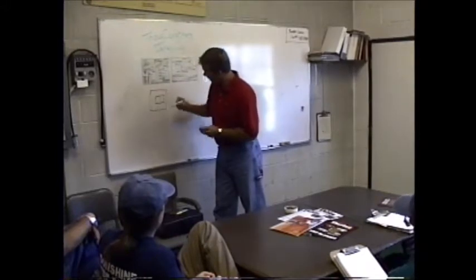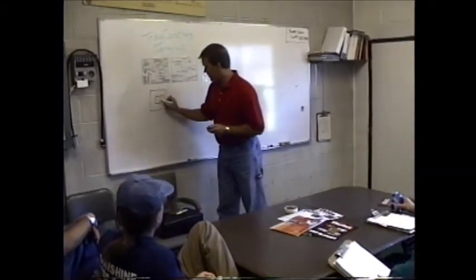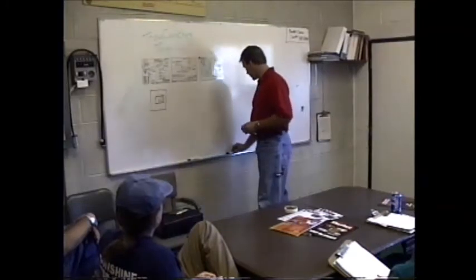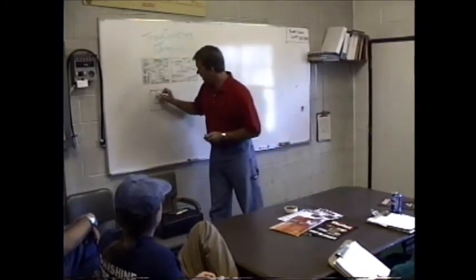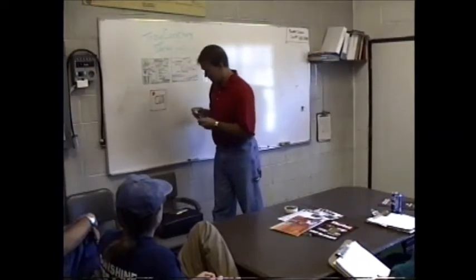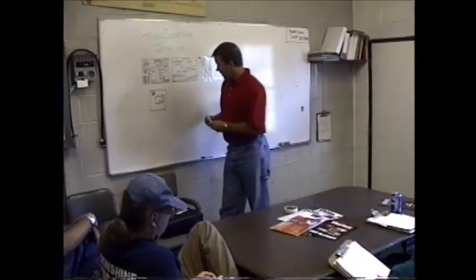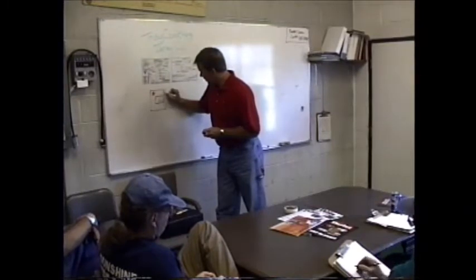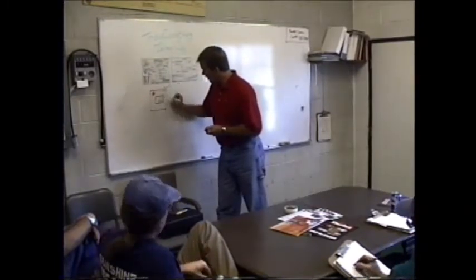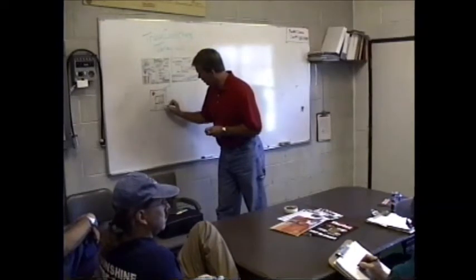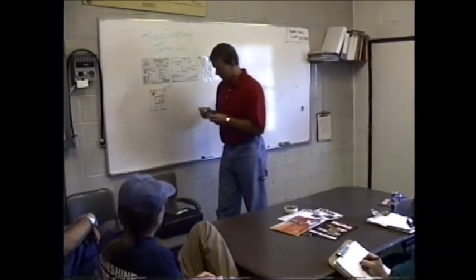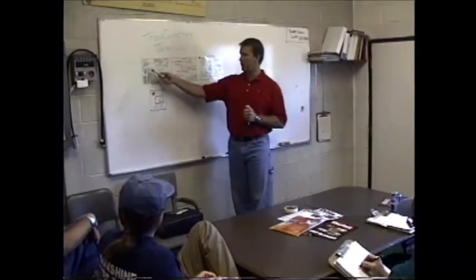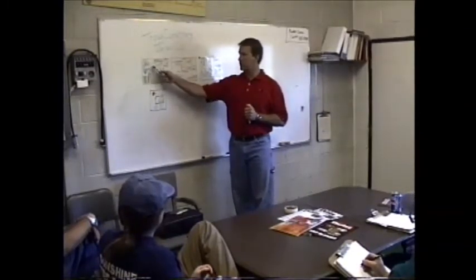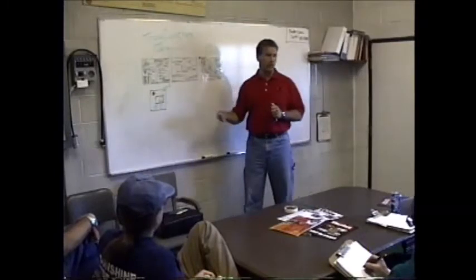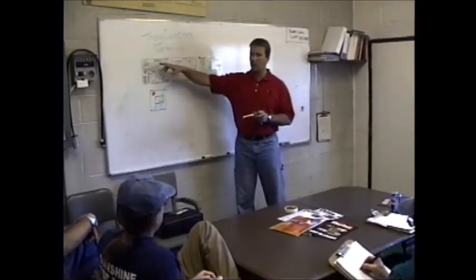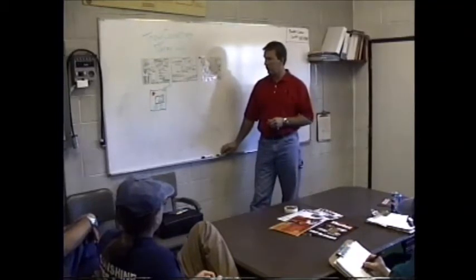Okay? And that's going to read your GPM. Let's just say 60 is what it's going to be showing for GPM. Up in that upper left-hand corner, there's a red button, okay? And in this corner, there's another button called Select. And down in these two corner buttons, you have a down arrow and an up arrow. Okay, this is the Foam Pro controller that reads this flow meter. When it starts to spin, it's going to send a signal to this device telling you exactly how many GPM are going to any one or all four of those different lines. Okay?